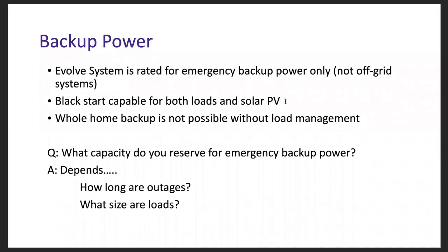Whole home backup is not possible without load management, and really is sort of a thorn in most people's side. Whole home backup to me, I think, is more of a fiction. If you've got to turn off loads when you go to backup mode, that's not the whole home. But anyway, the interconnection of our system and the design architecture really excludes whole home backup or the use of load control panels in the event that a customer wants to have the entire panel selectable.